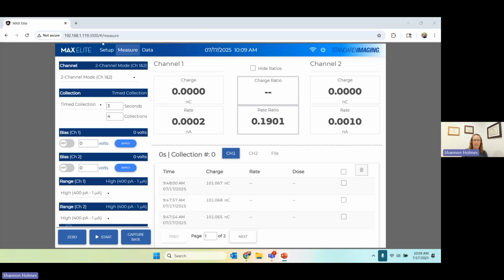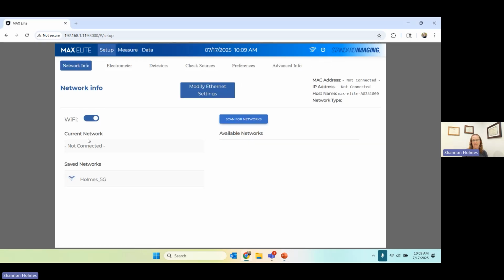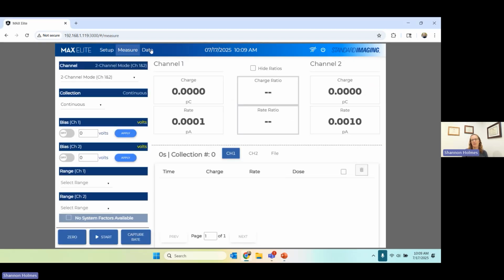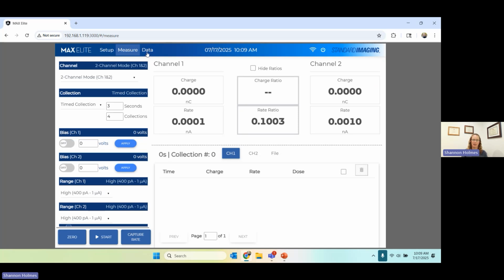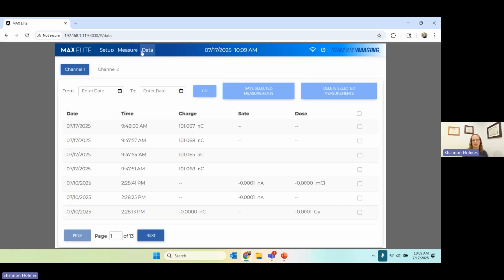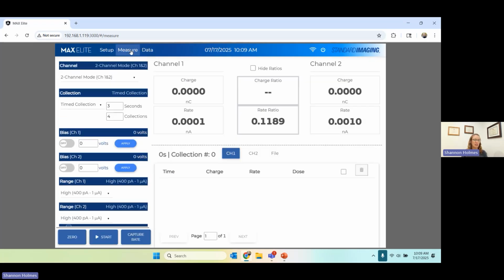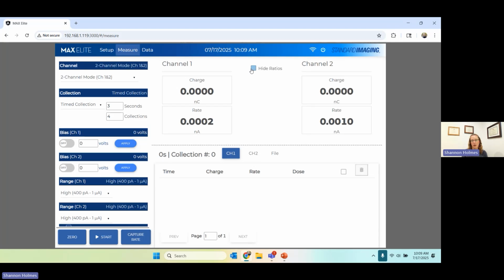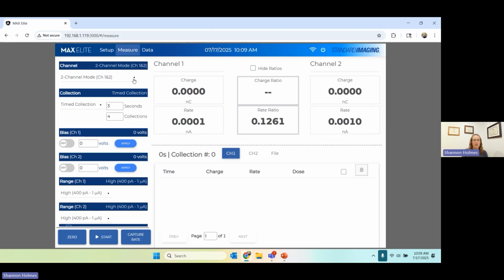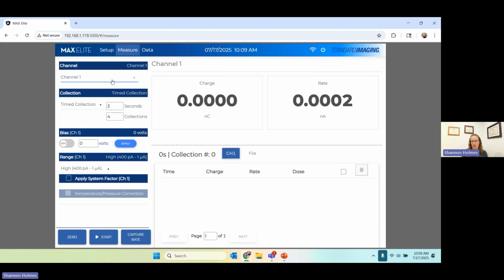So the basic interface here has 3 tabs. We have a setup tab, we have a measure tab, and then of course the data tab where you would have the history of your measurements available. The measure tab is where you spend most of your time, I'm sure. I have a 2-channel electrometer hooked up right now, so there's a display here of 2 channels. The ratios between those measurements, if that's of interest to you, are shown by default, but can be hidden if you don't want to see them. If I'm only using 1 channel, I can switch to just a single channel mode and have a cleaner interface that way as well.